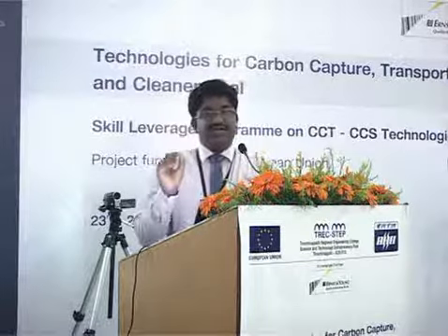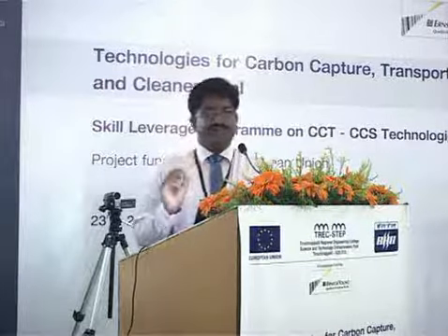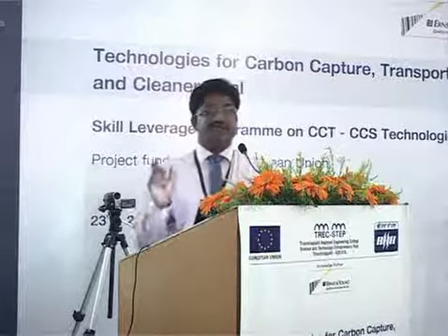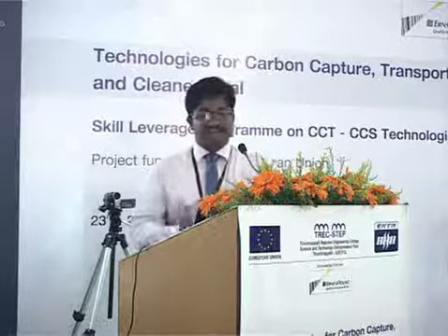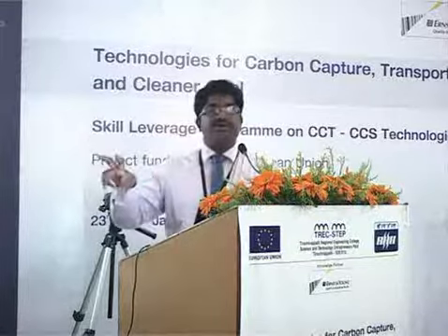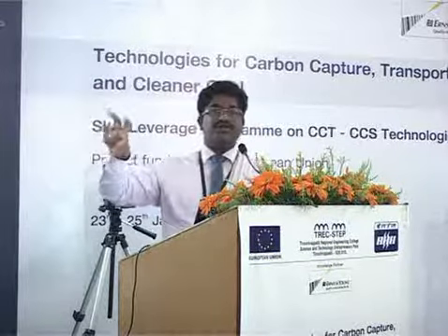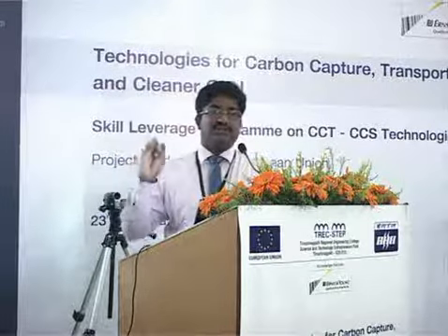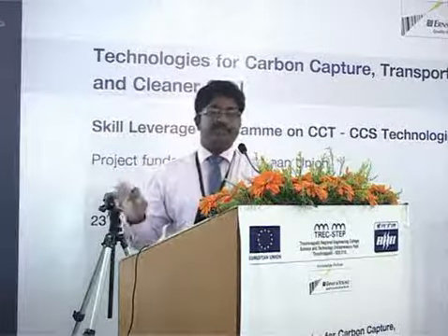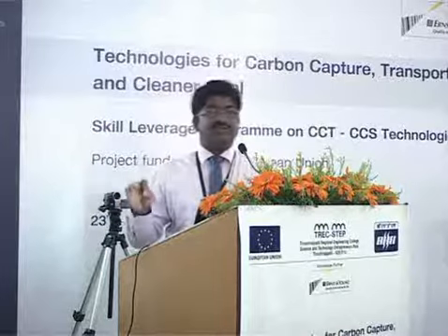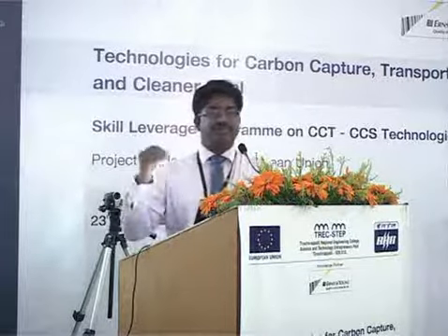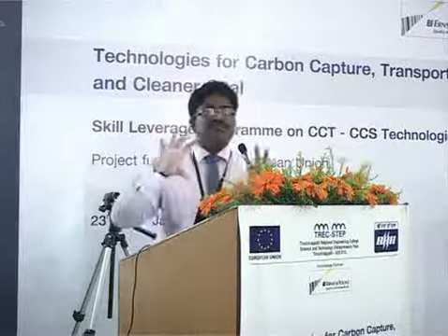The prime thing is that there is something called monitoring. Monitoring in the sense that we need to monitor certain parameters to evaluate your emission reductions. Say, in this particular case, I need to put up a check meter to monitor how much electricity is being generated. That's number one. Number two, I need to monitor the gross calorific value of coal on a monthly basis. Three, I need to monitor the ultimate analysis and proximate analysis of coal on a frequency basis. Then comes four, what transportation emissions are happening because of my project activity. So these are some of the things which you have to monitor.